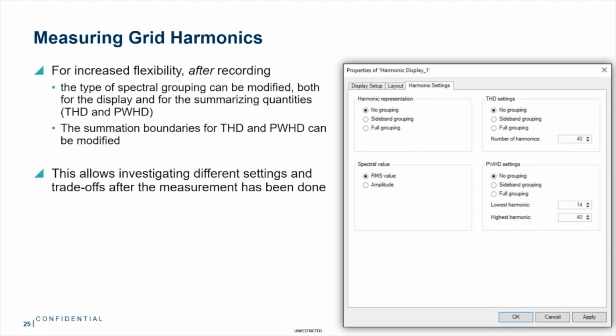So you can very easily change the way that you measured, from full grouping to, for example, no grouping, and then you get a different set of harmonics, different heights at least. And you can do the same for the THD and partially weighted harmonic distortion. So after the fact, you can still change the number of harmonics that you are using for THD and also what type of grouping that you are using. That gives you a lot of flexibility after the fact. So we think that's a nice feature.